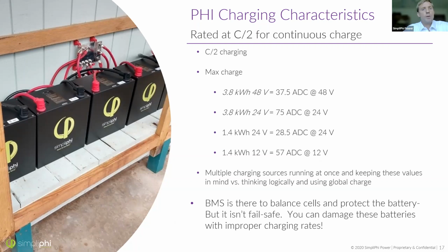Keep in mind that our 24 volt Phi battery, same with the Amplify, the Amplify and the Phi batteries, the 24 volt Phi battery is 150 amps of capacity. If you discharge that in 2 hours or charge that in 2 hours, you'd be looking at 75 amps. That's the maximum rate, but that's per battery, right? So our most common battery, the 3.8 kilowatt hour, 48 volt battery, has 75 amp hours of total charge. Divide that by 2 to charge it up in 2 hours, and the max rate of charge per battery is 37.5 amps.